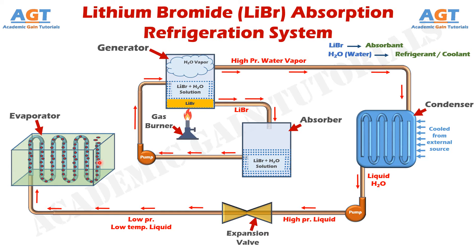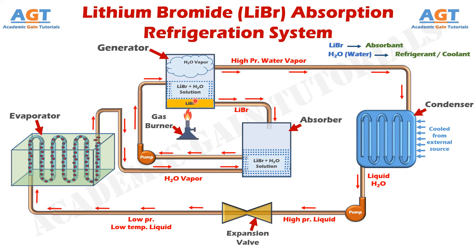After that, this low pressure water vapor will leave the evaporator and enter the absorber again through this connecting pipe. This low pressure water vapor will then form a solution with the lithium bromide present in the absorber. The pump will again send this solution to the generator, where the water and lithium bromide will be separated again by heat, and the whole cycle will keep repeating again and again. Thus refrigeration will be happening continuously in the evaporator. This is how a lithium bromide absorption refrigeration system works.